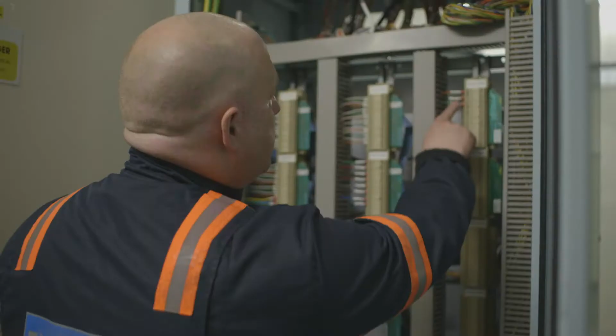CLASS stands for Customer Load Active System Services, and it's about understanding the relationship between voltage and demand. The idea behind CLASS is that you can alter voltage on the system and alter the demand, which means you can have local changes, so that the substation doesn't need its assets enhanced or renewed, saving customers money, or it can help the national grid balance supply and demand.